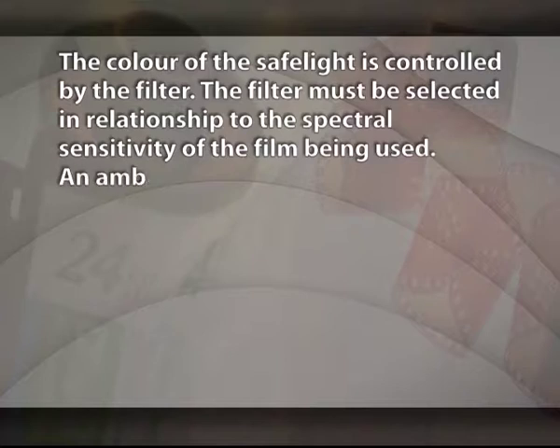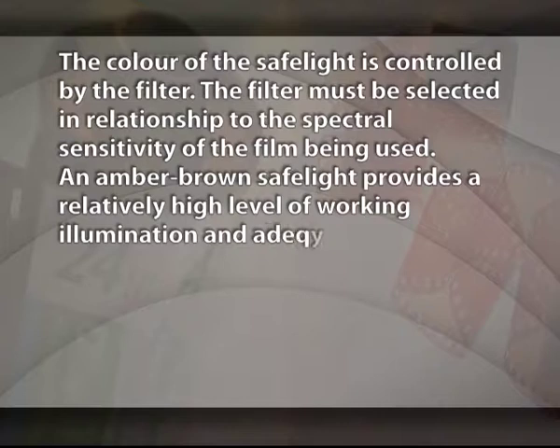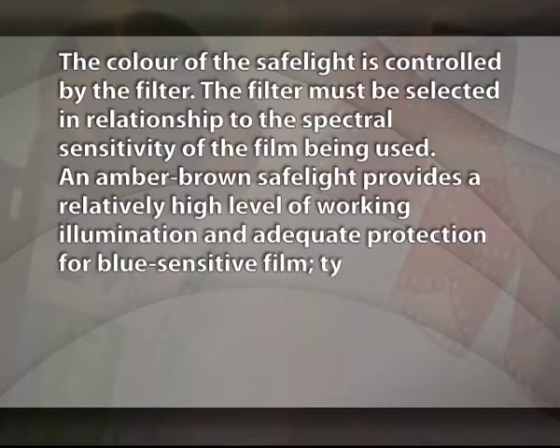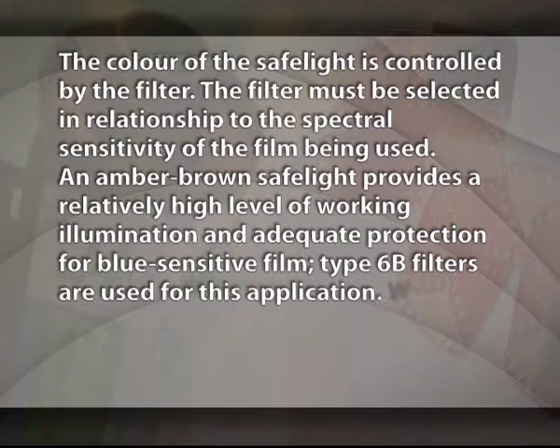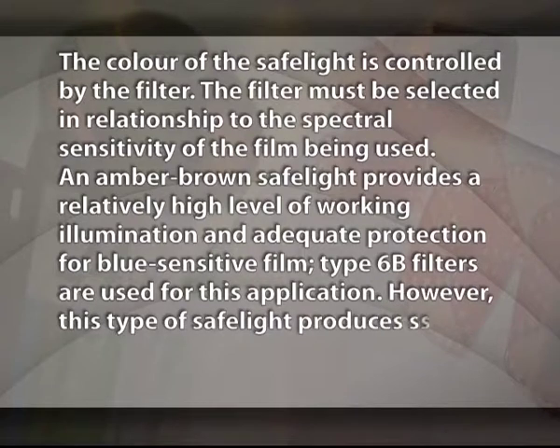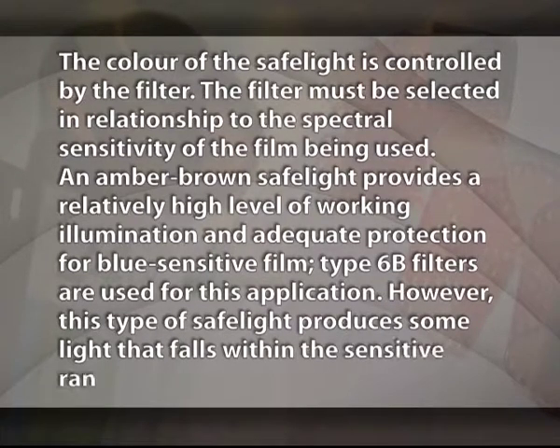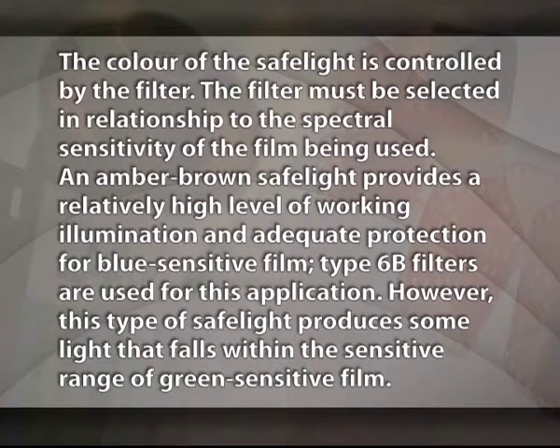The color of the safe light is controlled by the filter. The filter must be selected in relationship to the spectral sensitivity of the film being used. An amber-brown safe light provides a relatively high level of working illumination and adequate protection for blue sensitive film. Type 6B filters are used for this application. However, this type of safe light produces some light that falls within the sensitive range of green sensitive film. A red safe light is required when working with green sensitive films. Type GBX filters are used for this purpose.